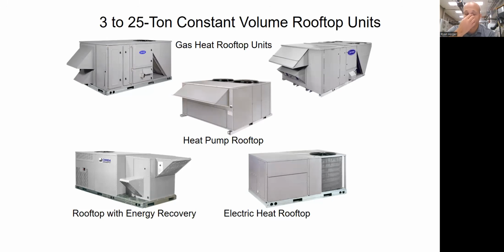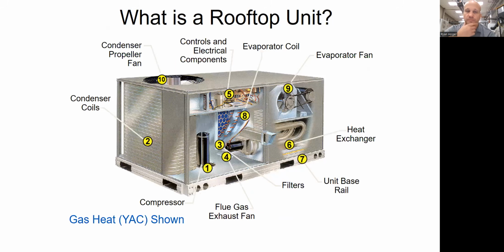About 54% of the United States is heated, I should say is cooled with packaged rooftop units. It's a little bit less for heating for various reasons, but from a cooling standpoint, 54% of the country for commercial buildings is being cooled with one of these units. So it is a lot of applications. We're going to focus on smaller stuff right now, which typically means 3 tons of cooling capacity up to like 20, 25, 30 tons of capacity. When you get bigger than that, you're into more customized type stuff, or at least semi-custom type stuff.